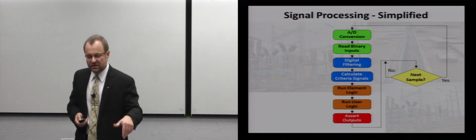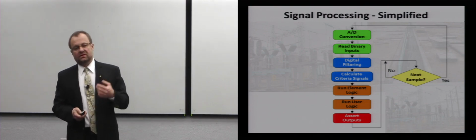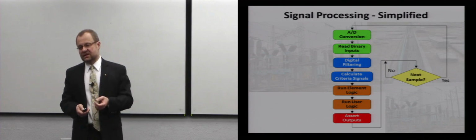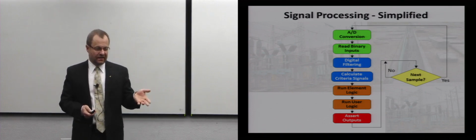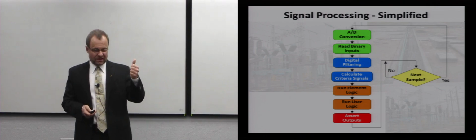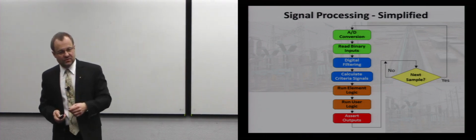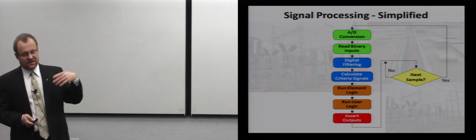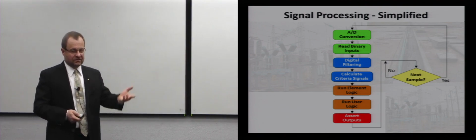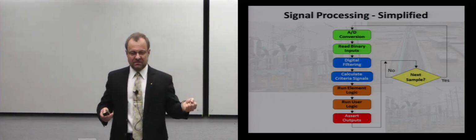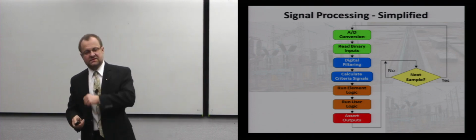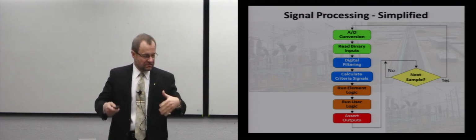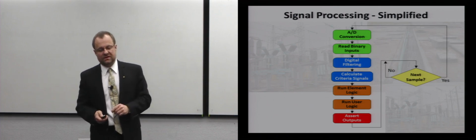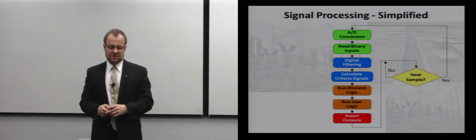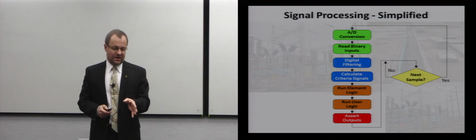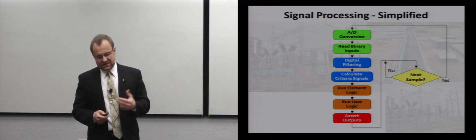Now, this is only about the main protection function. On top of that, I may have tasks that have to do with HMI, with reading those push buttons, with talking with a SCADA computer. It comes to me and says, give me the phase A magnitude, and I have to parse the message. I have to get my phase A magnitude, put it in a packet, and say, here is your phase A magnitude. So that's the nature of the multifunction device. But for protection, this is pretty much it, right? Now, except nobody does it this way. It would be unnecessarily complicated.